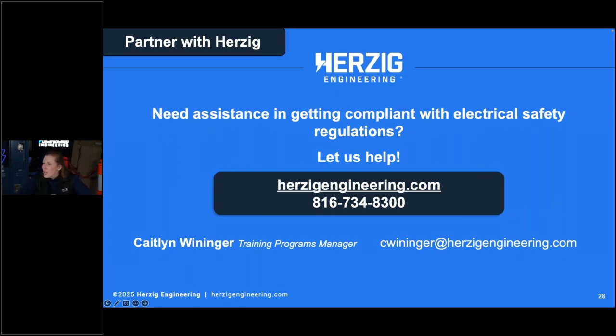Got another question here: are there IR cameras that allow the person scanning to stay outside of the arc flash boundary? I want to say yes. There are definitely cameras with high enough image capability that you can stand back further and even zoom in a bit to stay outside the arc flash boundary. Two things though: first, you have to know what the boundary is. It's very dependent on that system and equipment, so you have to have the study done to figure out what the boundary even is. If you have that, great, I'll move on.